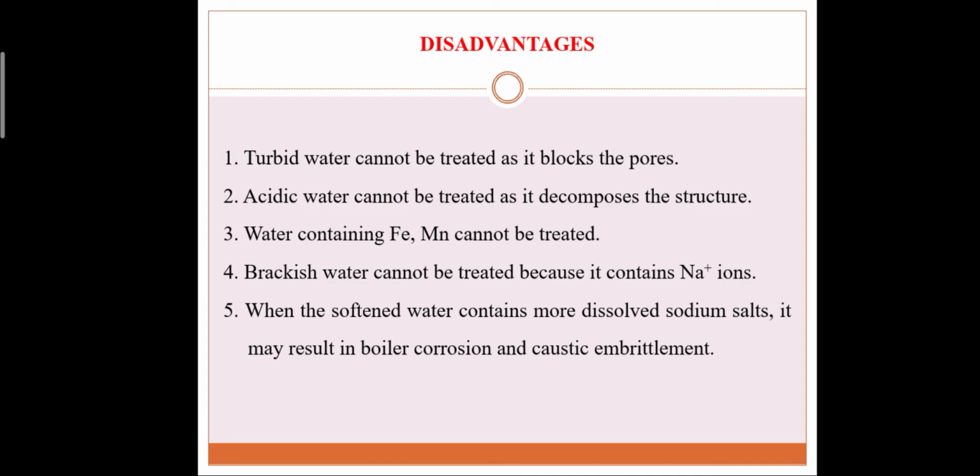Finally, we cannot use the obtained soft water from this method in boilers because the obtained soft water contains more dissolved sodium salts in it. When this water is boiled in boilers, it may cause boiler corrosion and caustic embrittlement.